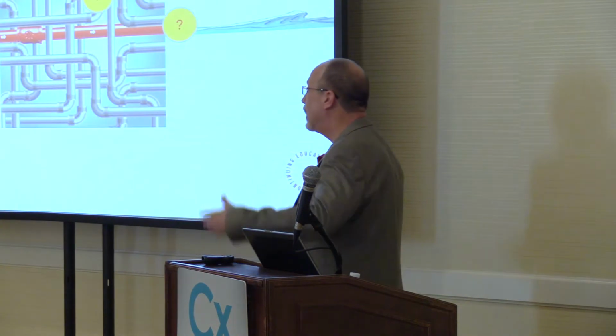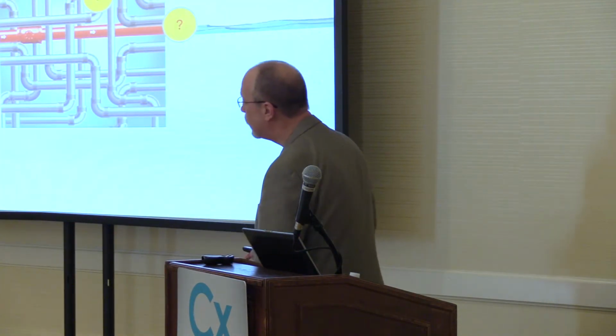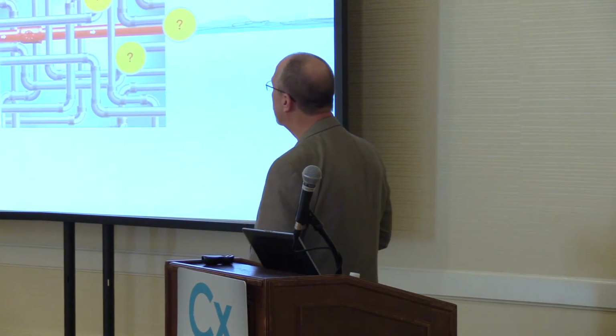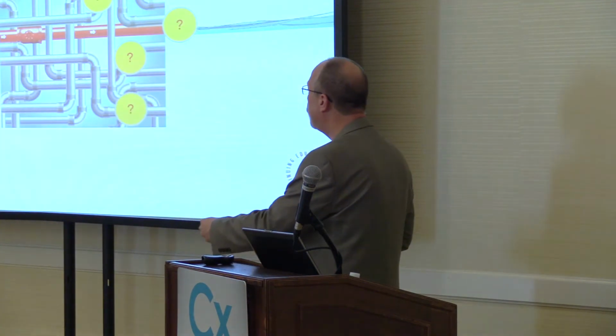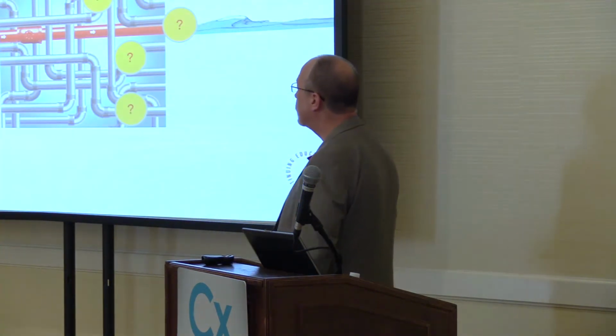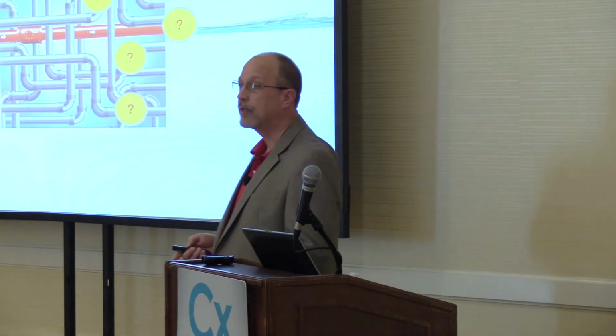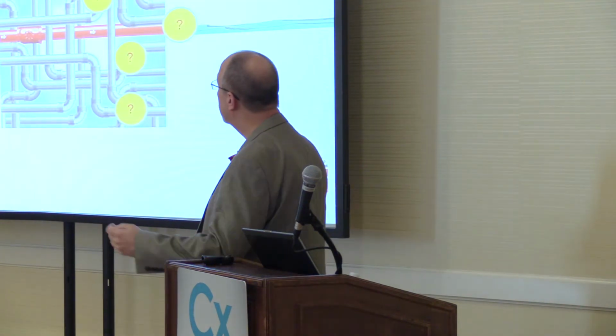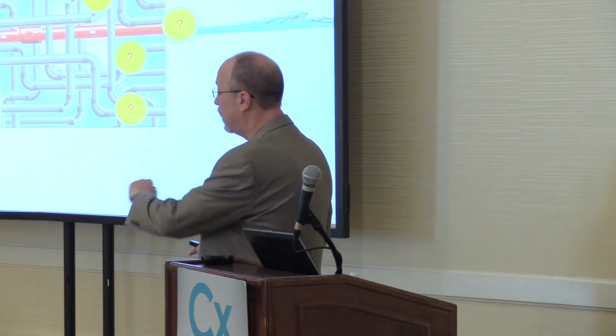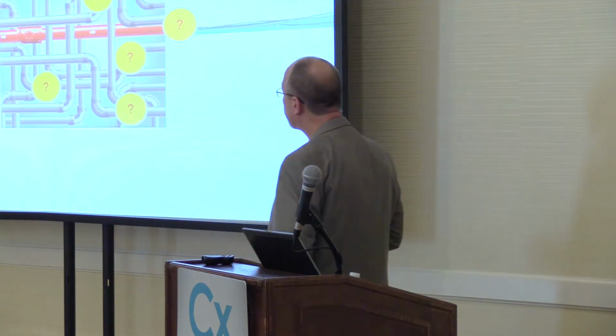in this case there, say maybe I've got a car wash situation and that Chevy pickup truck just drove away with 40 gallons of water in the back of it and I'm recycling it. My gazinta doesn't equal my gazada, so we have to have individual sub-metering to find out the individual zones to do this. So more and more people are asking us to monitor the effluent facilities. In some cases it's difficult because there's partially filled pipes. So there's different flow meters and different technologies for those particular applications.